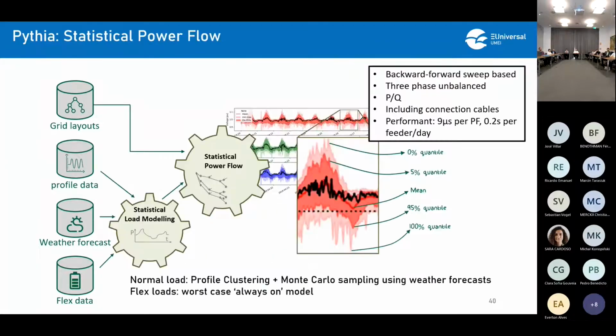The first step is a statistical power flow. We could do an exact power flow, but that would never work because of load uncertainty. So we've developed a statistical power flow specifically for the low voltage grid. That means it has to be a three-phase system, with both active and reactive power, using backward-forward sweep methods, for those interested.